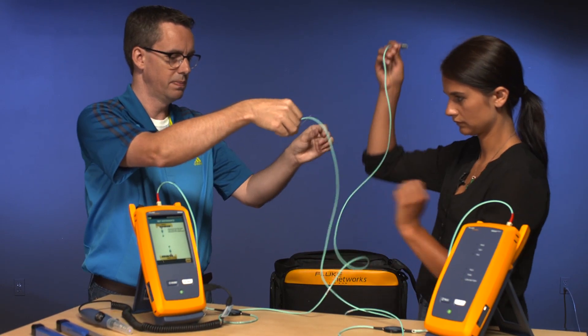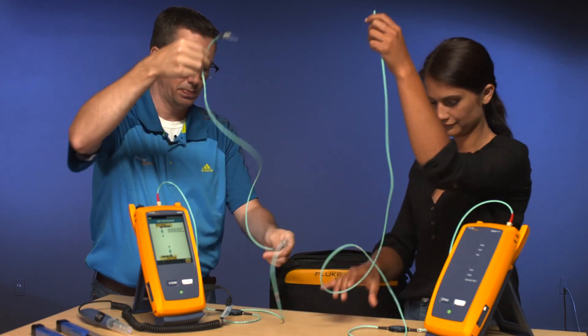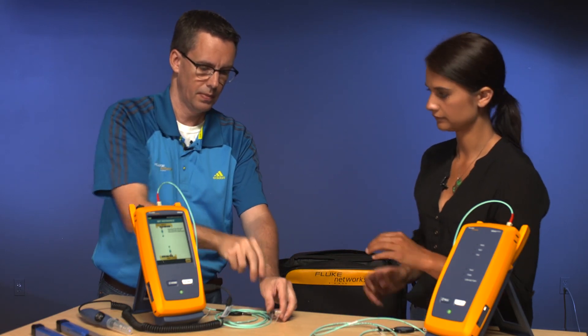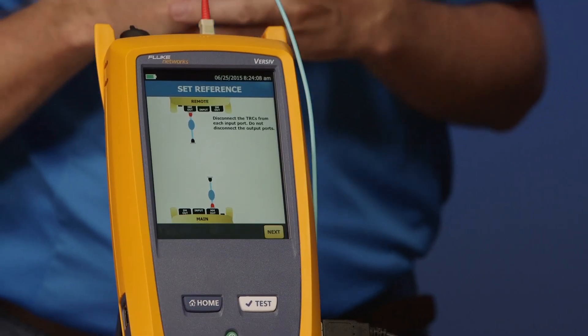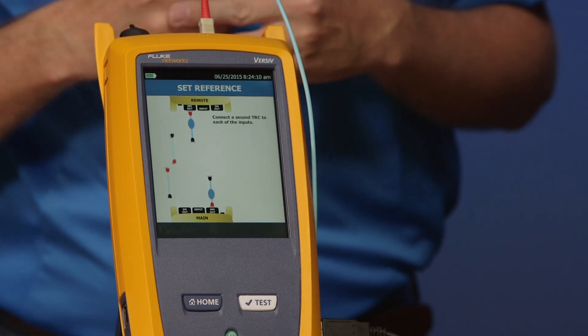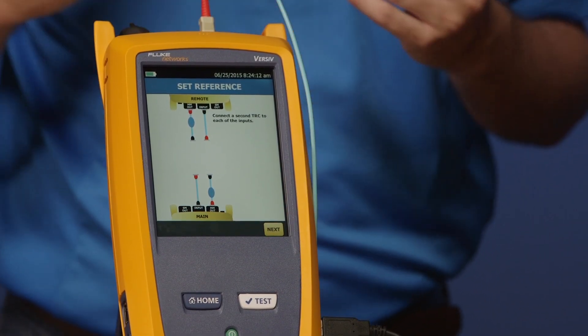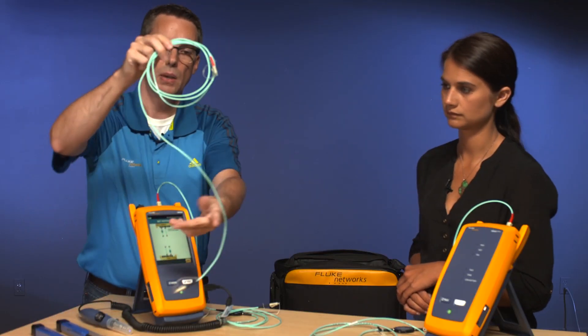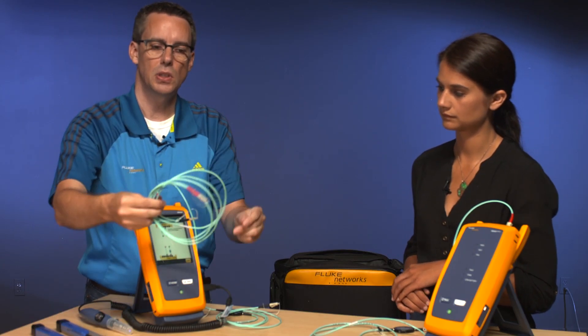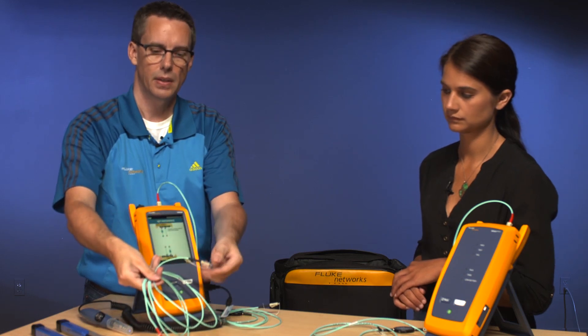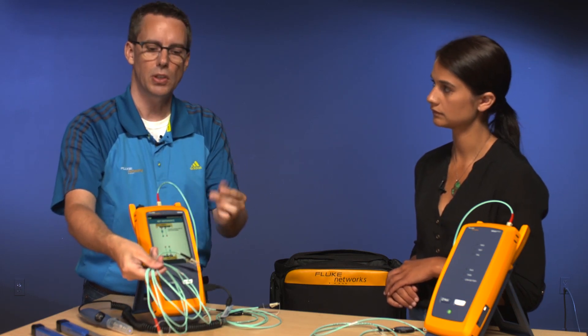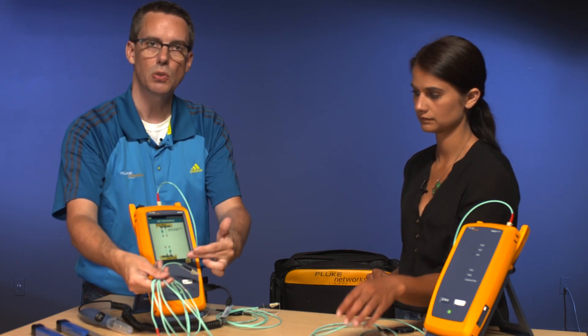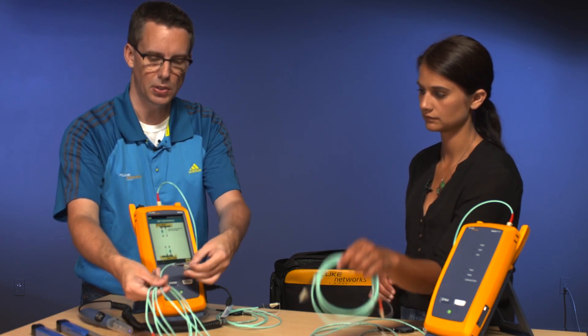Let's do a swap and lay them down on the table. Go ahead and tap Next. It's asking us to take our other cords and place them in the input ports. Again, we've got a 50-50 chance of doing this right — one end is red, one end is black. Since it's the input port and that's the cold side, we'll put the black into the input port, noting that it's also color-coded on the screen. So let's take our black connector and plug it into the input port.